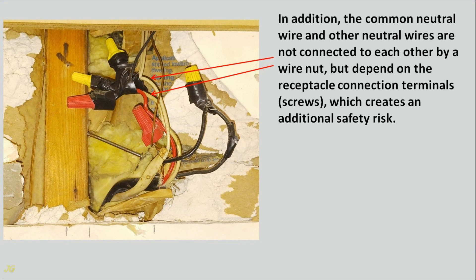In addition, the common neutral wire and other neutral wires are not connected to each other by a wire nut, but depend on the receptacle connection terminals screws, which creates an additional safety risk.